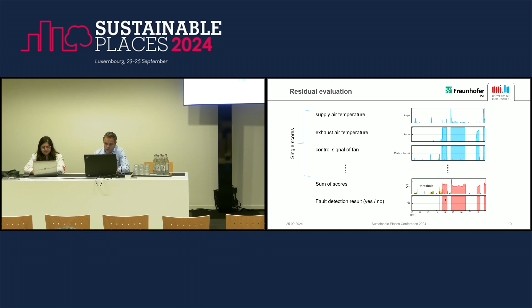This is done for all the variables, and at the end of the day we sum up all the scores. We also set a threshold empirically, I think at 1.5 for all the variables, and if this threshold is exceeded, it generates a fault signal.